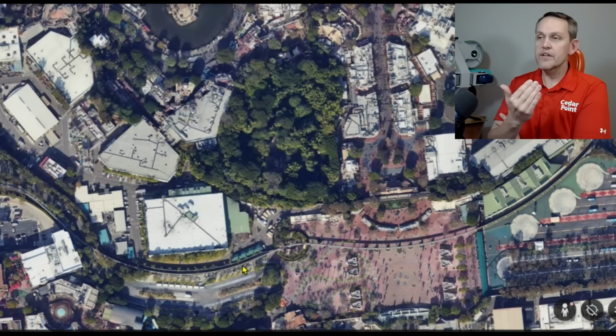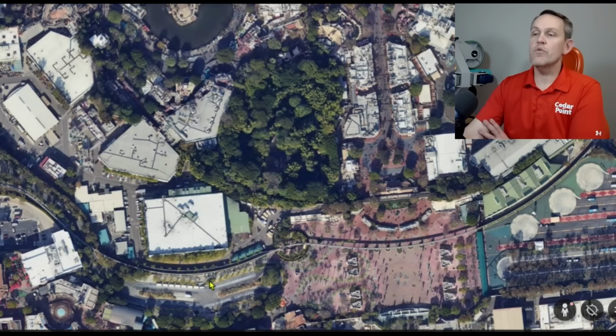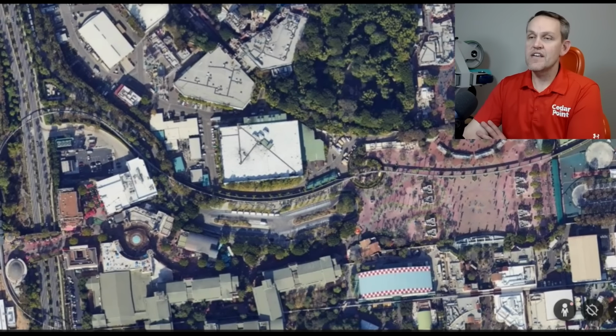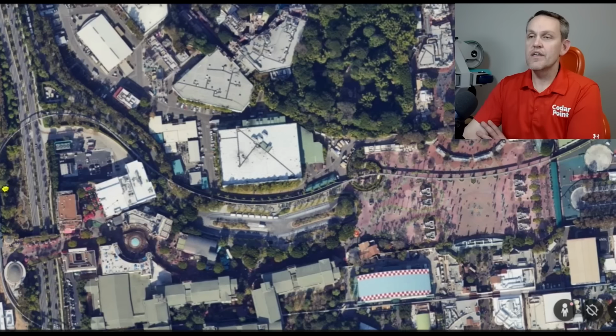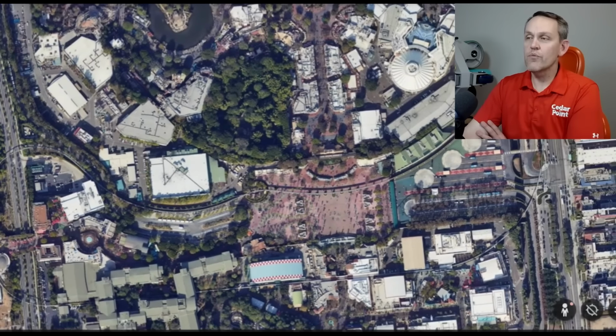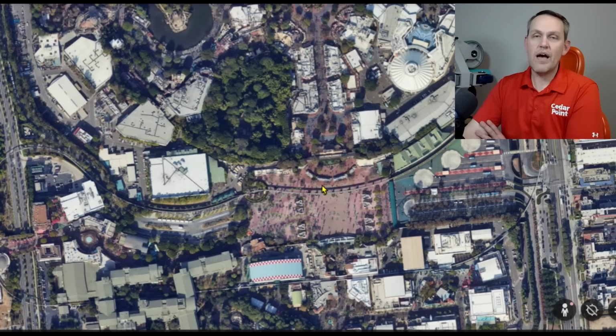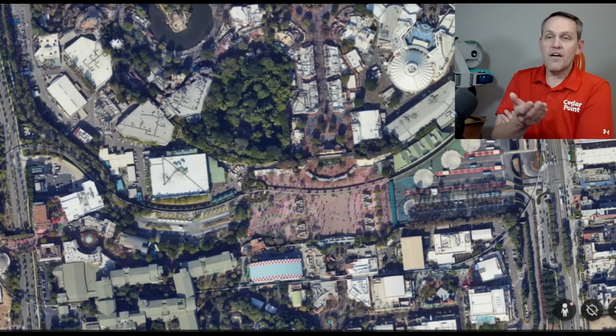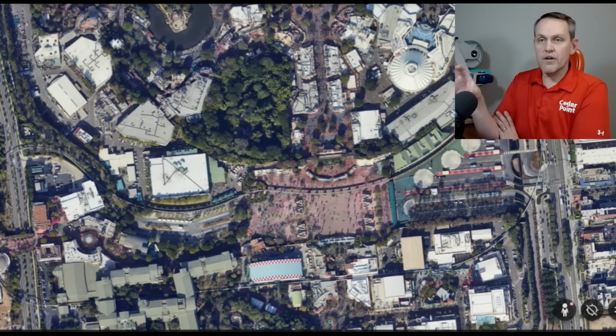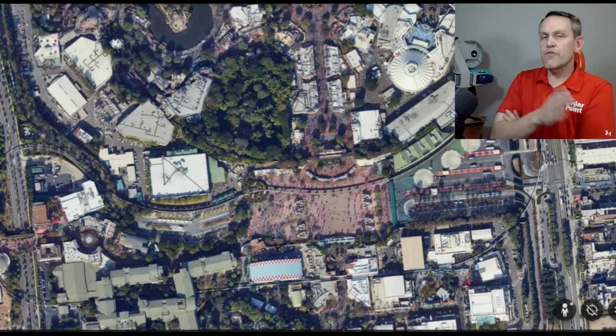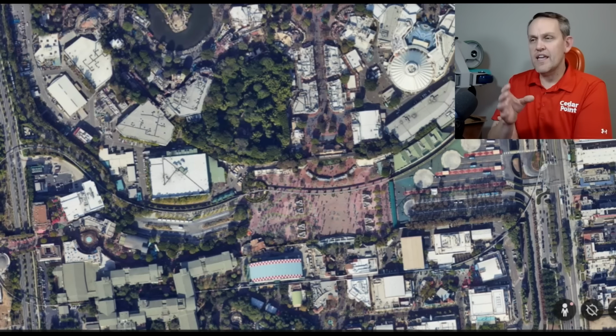There's tons of what are called home run wiring. These wires basically go from a connector, say at a monorail station, through a conduit, all the way back to a power substation. It could be that different substations feed different sections of the ride, but from a safety point of view you have to mechanically or electrically tie all those together so that when an e-stop is hit, it drops out everything along the way.